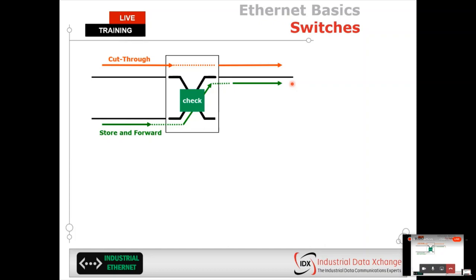Store and forward switches are a little bit more reliable, as they're not going to pass through a message if that message is damaged. One of the main checks he's doing on the telegram, apart from the length of it, is checking something called a CRC. A CRC is a check in an Ethernet message to see whether a message has been received in the same formation that it was sent out, so you can check if anything's been damaged or changed.